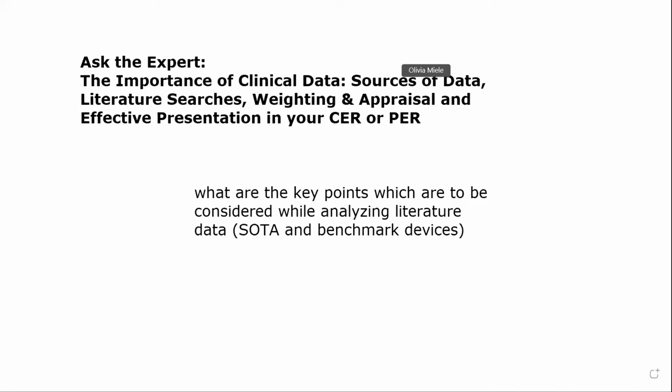The key point here is that you have established somewhere in your CER or PER the acceptance criteria against which you analyze your data, subject device data. And if you need or want more information on how to identify acceptance criteria, where it comes from, even what it is, I don't have enough time to explain that on this call, but we just put a webinar on yesterday about that, and we've got a lot of resources on our website about acceptance criteria and what it means.